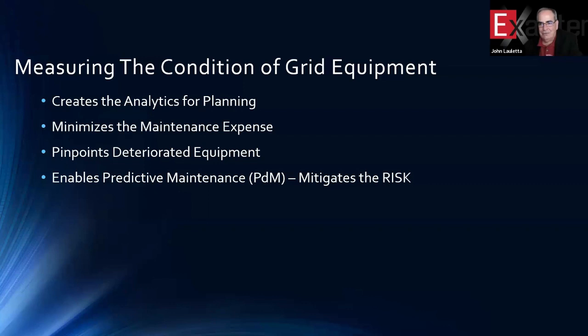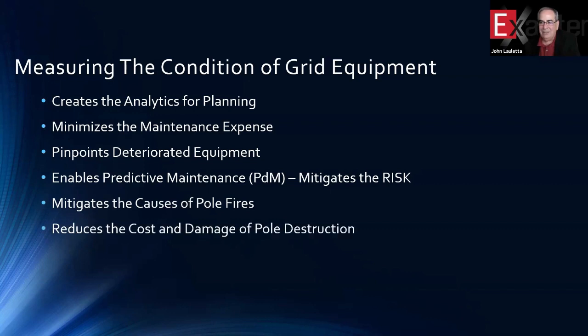And this predictive strategy mitigates risk because now your linemen aren't working in an emergency situation. They're working when they have schedules, they know what they're going to do, and they can do it during daylight hours. You can mitigate the cause of pole fires, and of course, the pole fire itself can cause a lot of other costs and outage durations that you just don't want. At that utility we were working on, they said the average cost of a pole fire was $25,000. The average cost of changing an insulator on a schedule, $500. Much better deal.